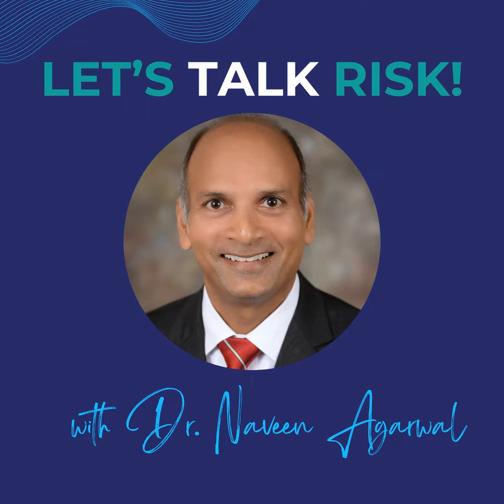Thank you. Now, I would say to this, there might be situations where you don't have enough understanding of the entire system, where you cannot project that sequence of events, when you cannot be sure, or reasonably sure, about what might happen, what might not happen, and you want to take a conservative approach. Got it. There is nothing wrong in assuming a conservative approach. What you have to then step back and ask is, am I doing everything I can to control the risk? And if the answer is yes, then is it still worthwhile? Which means, do the benefits outweigh the residual risk? So Darpan, excellent question. I know there's a problem in the industry, a lot of challenges, but I want you guys to know that you know your system better than anybody else, okay? So you ask the question, are we doing everything we can that is practicable? Okay, let me correct myself. Practicable. We leave it at that, guys.